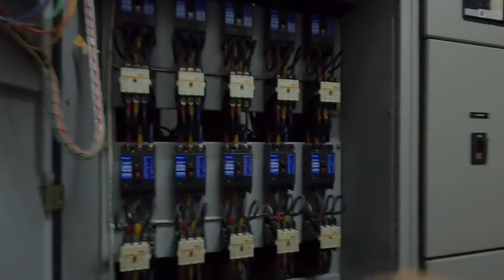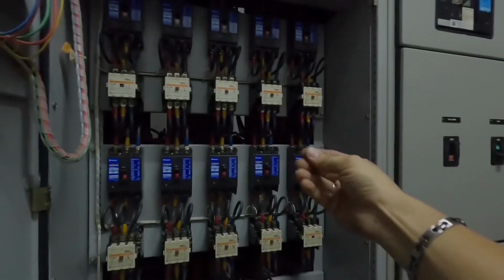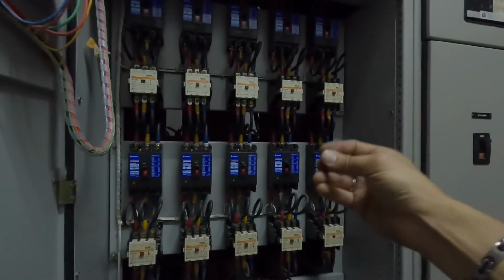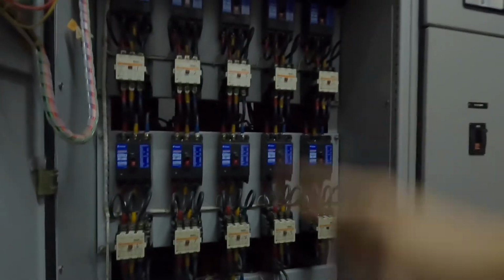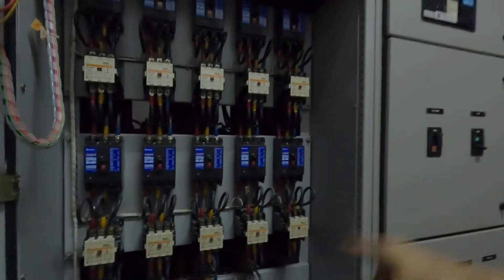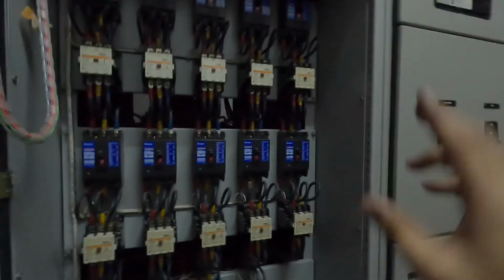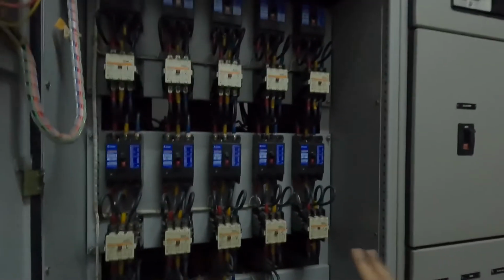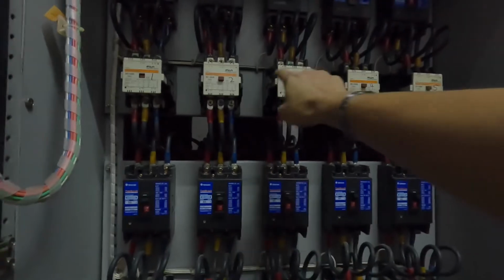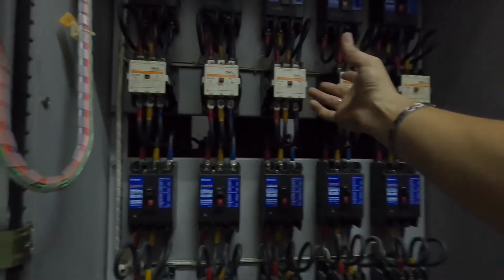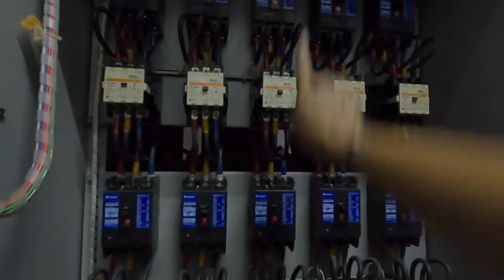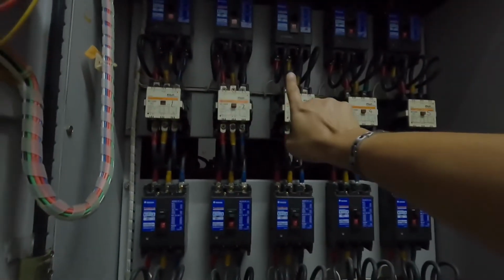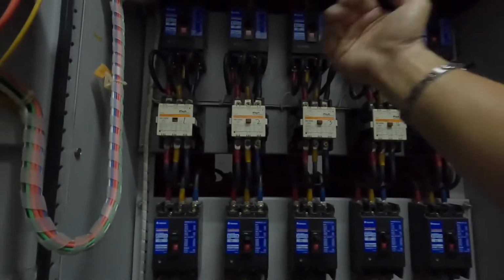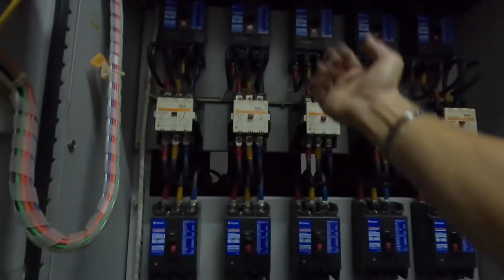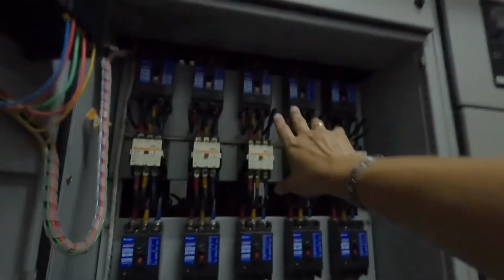Just like a motor, when a pump or any motor is running, there's a contactor holding it. When suddenly TNB has no power supply, the contactor will release, but your motor or your pump is still turning and it will become a generator. So to avoid the reverse power, when there's no power coming to the control system, this will release and open the circuit, so the reverse power cannot feed back to the upcoming system. So it won't clash with the sudden incoming power supply from the main source, and there won't be any reverse power.